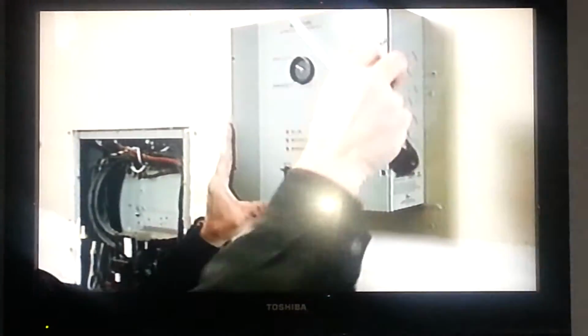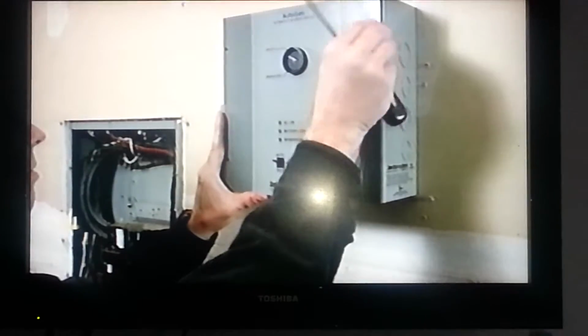First, you will need to install a double-pole circuit breaker in your service entrance panel. This circuit breaker will be used specifically for the ATS. When you have installed the circuit breaker, remove the cover on the ATS transfer switch. Remove the appropriate knockouts.